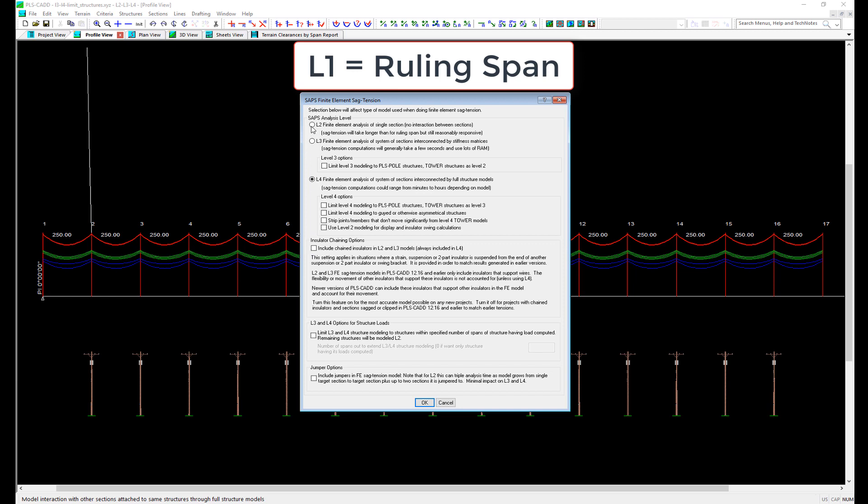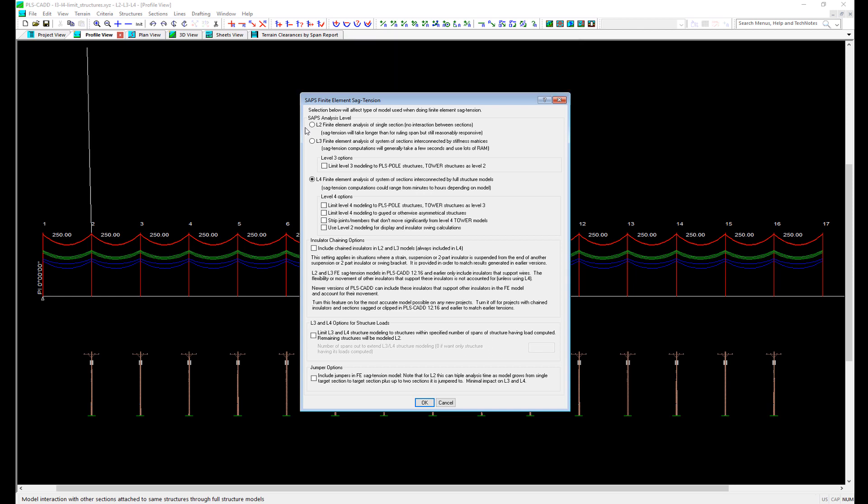In ruling span sag tension, the horizontal component of tension is always equal for any weather case, similar to putting the wire in pulleys or blocks. In reality, conductors are clipped in and there is a fixed length of wire in every span. This results in changes in tension between spans with changes in wind and ice loading as well as temperature.